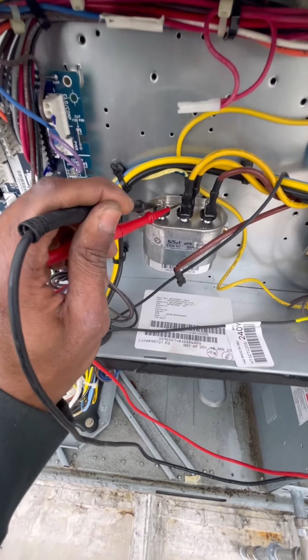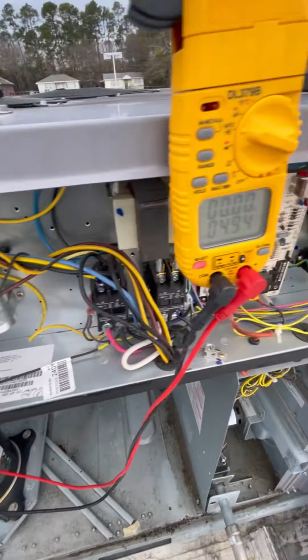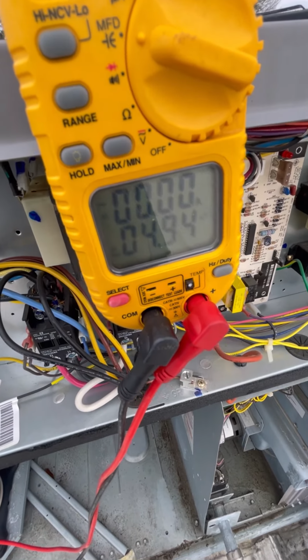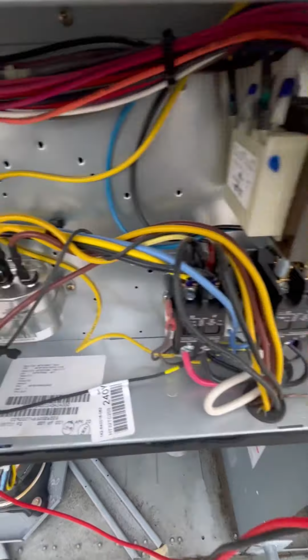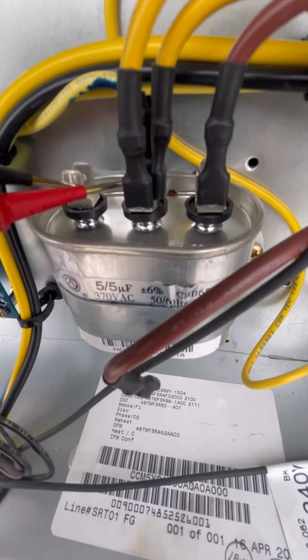Okay, so we got our test leads on our fan side right now, and it's reading 4.9 out of 5. It's plus or minus 6%, so we're in range.